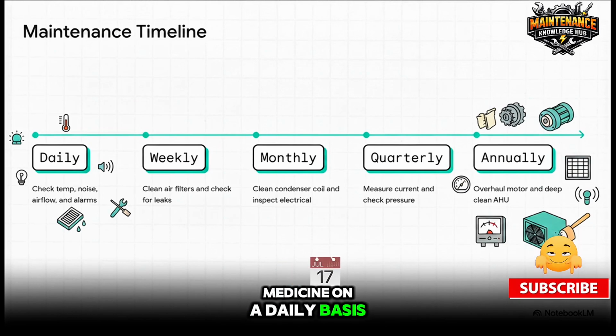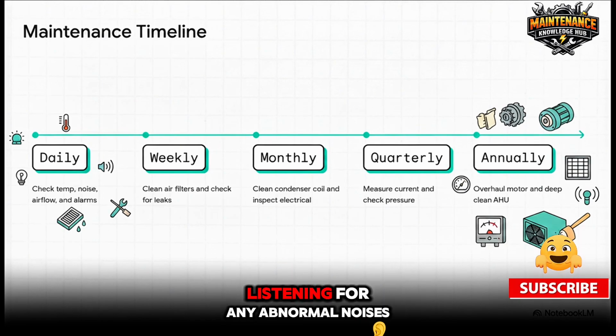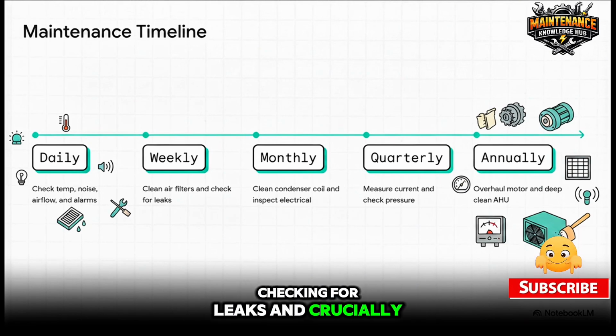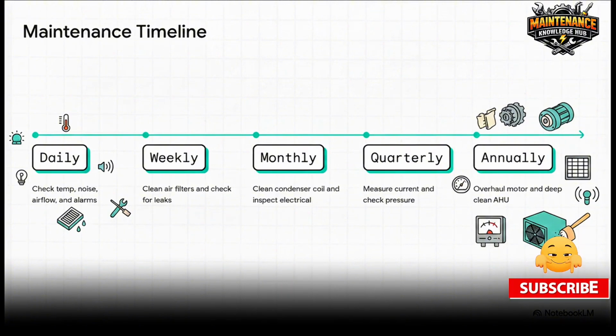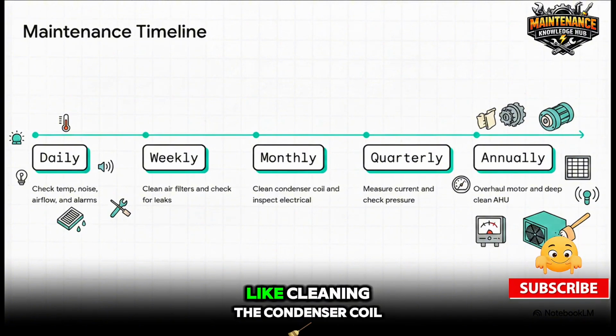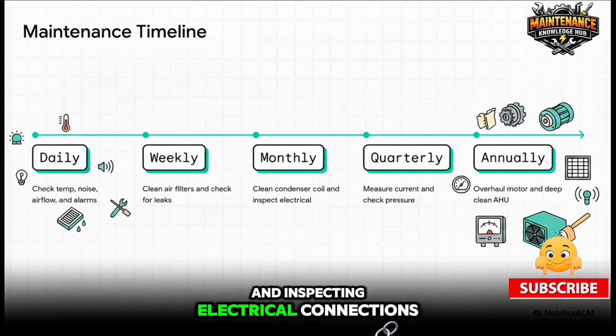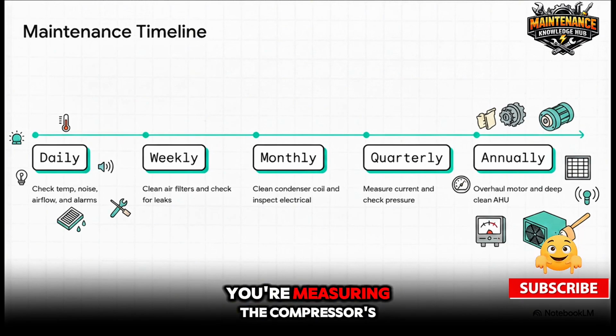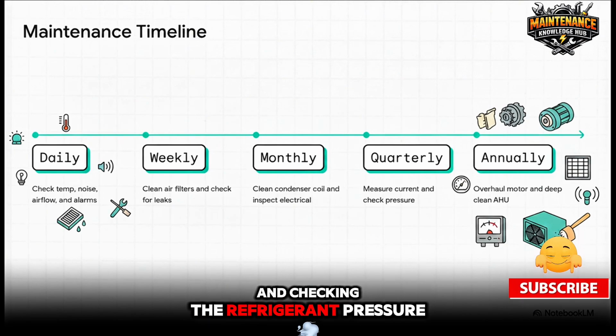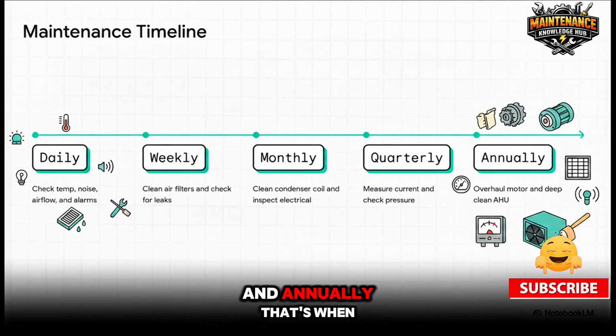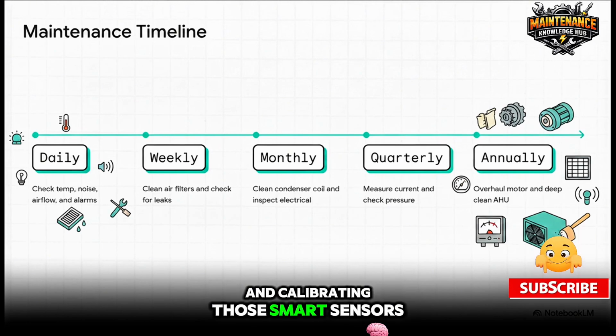On a daily basis, it's as simple as checking the temperature, listening for any abnormal noises or vibrations, and watching for control panel alarms. Weekly, you should be checking for leaks and, crucially, cleaning those air filters. Monthly tasks get a bit more involved, like cleaning the condenser coil and inspecting electrical connections. Quarterly, you're measuring the compressor's electrical current and checking the refrigerant pressure. And annually, that's when it's time for the deep work, overhauling the blower motor, performing a deep clean of the AHU, and calibrating those smart sensors.